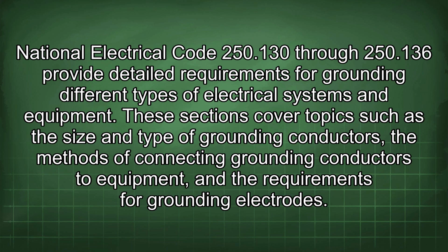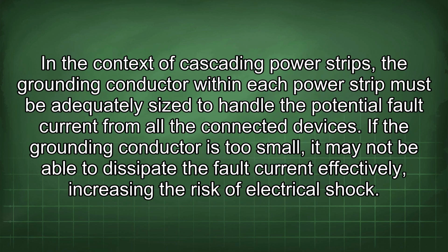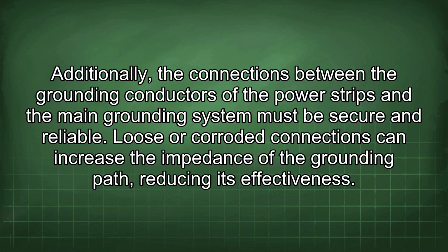These sections cover topics such as the size and type of grounding conductors, the methods of connecting grounding conductors to equipment, and the requirements for grounding electrodes. In the context of cascading power strips, the grounding conductor within each power strip must be adequately sized to handle the potential fault current from all the connected devices. If the grounding conductor is too small, it may not be able to dissipate the fault current effectively, increasing the risk of electrical shock. Additionally, the connections between the grounding conductors of the power strips and the main grounding system must be secure and reliable. Loose or corroded connections can increase the impedance of the grounding path, reducing its effectiveness.